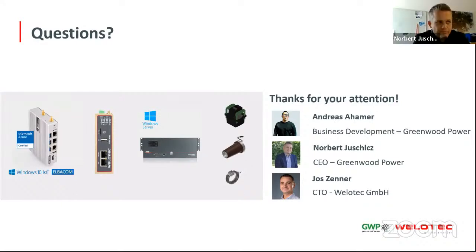Yeah, one big use case for sure, to have sensors and an IED inside a secondary ring main unit, is to have some kind of balance regulation. The best case is that you balance the voltage. You have some limits given by law, plus minus 10%, which must be held. And to keep this band under control, you could use the voltage sensors to make the measurement. You have 0.5% accuracy.